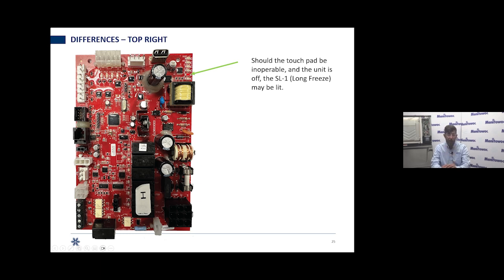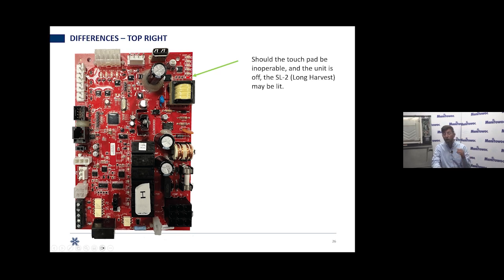If one of these two lights was lit, you could find out that this machine shut off on safety limit 1, as we show on the screen right now. That's long freeze. Or you could see the safety limit 2 long harvest light. Again, this is not present on the Indigo NXT. We have two safeties that shut the machine down.